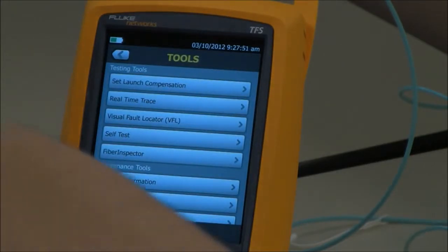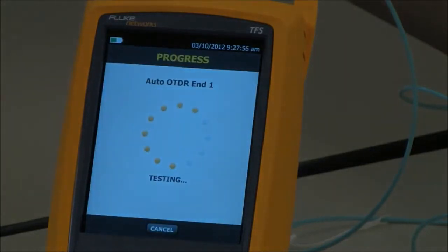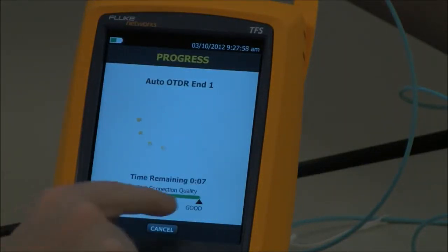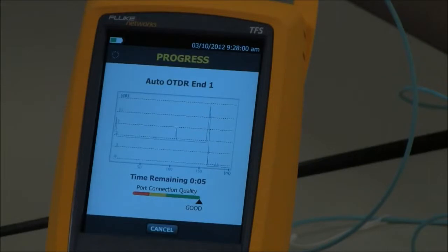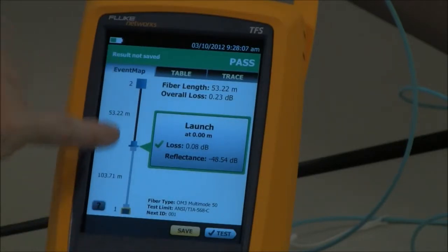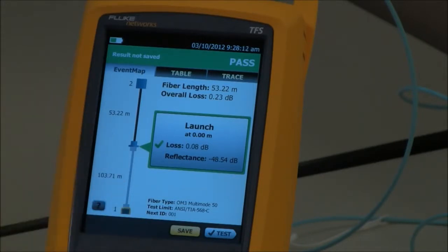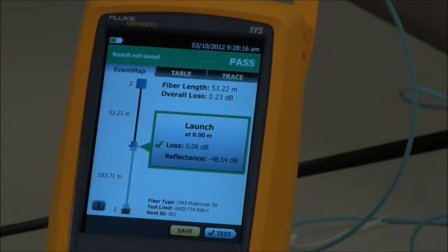Now I'm going to connect it into my link under test and hit the test key. OTDR port is good. Here's my OTDR trace, and here is my event map. My launch fiber compensation has been applied because it's grayed out, and my measured link here is 53.22 meters.